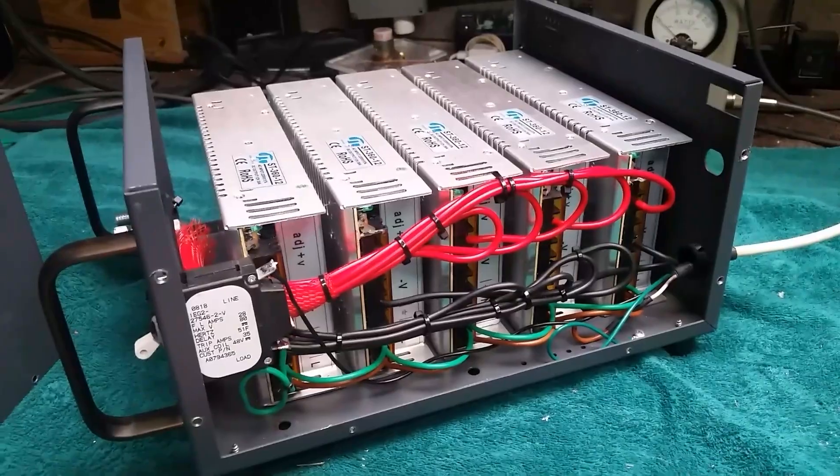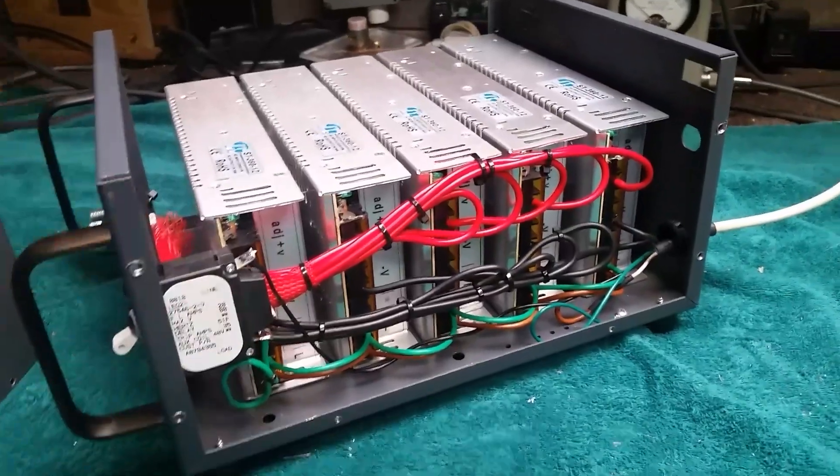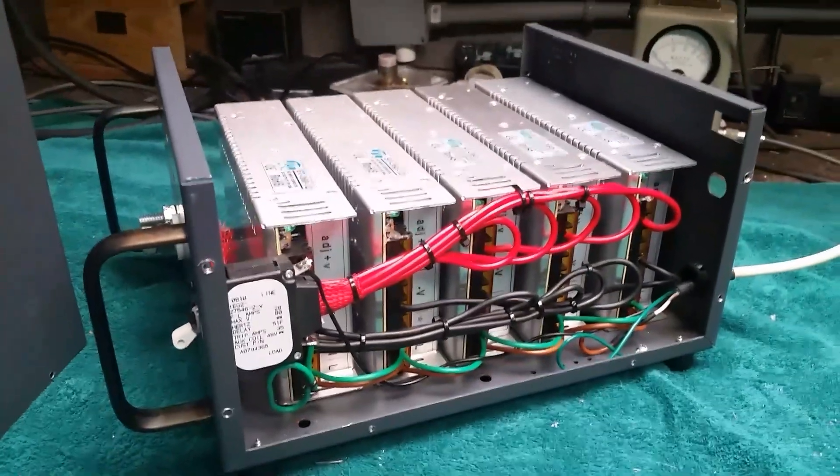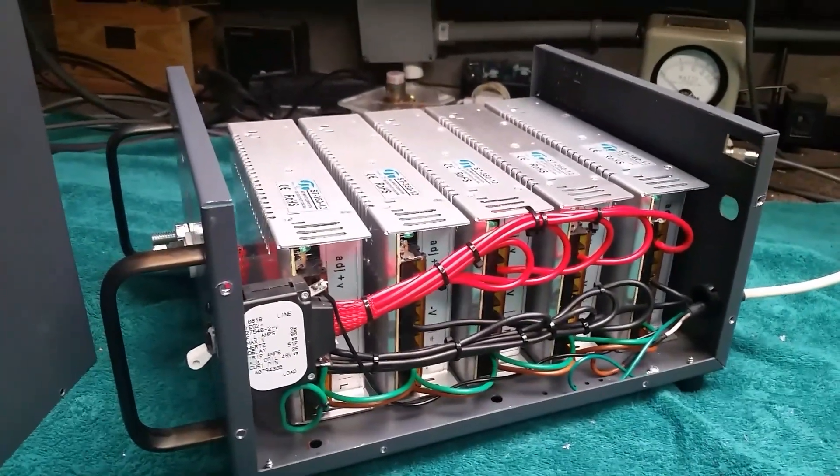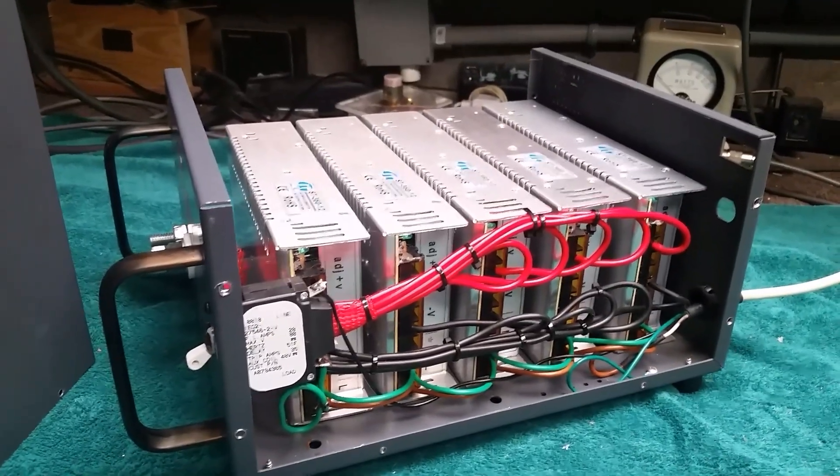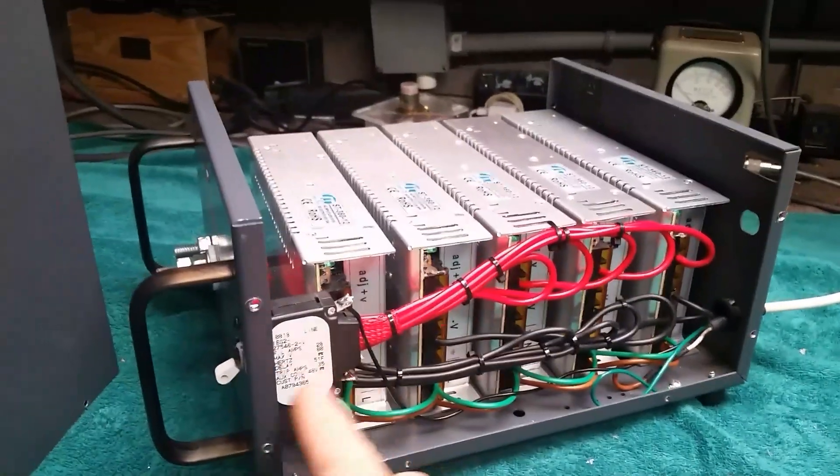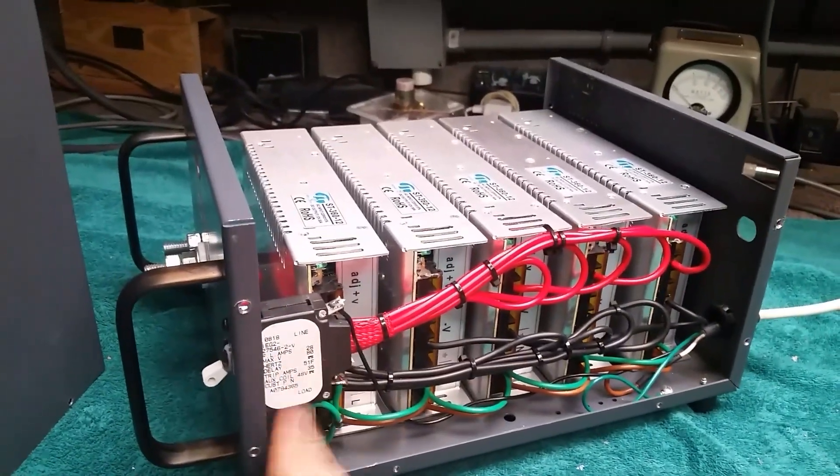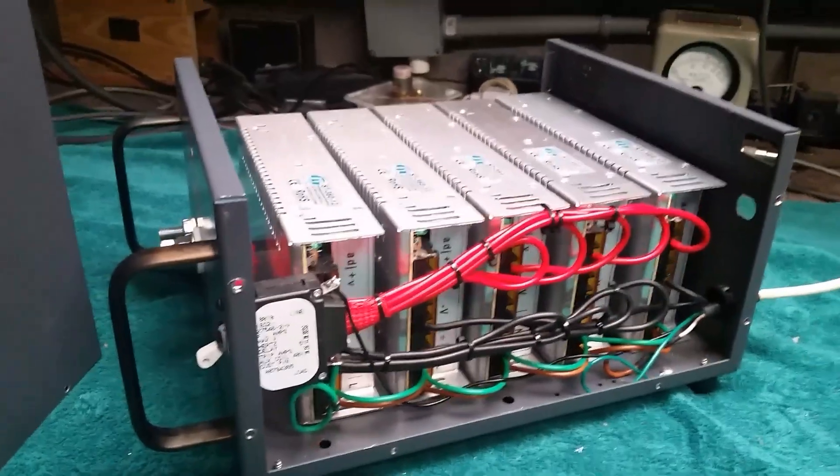But I've load tested it on my load tester and she is pulling up 180 amps and then the switch kicks out, so she's doing her job.